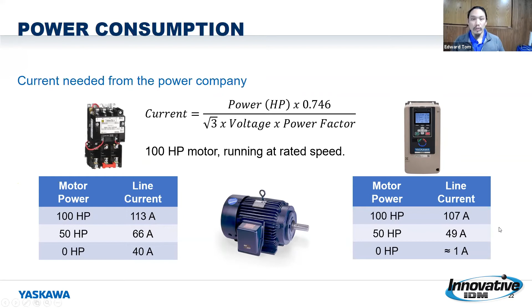On the VFD side, the reason why we're going to see lower line current is because that magnetizing current is still there on the motor side, but the drive will shield that a little bit, because now it's just circulating inside the drive. We don't need anything on the input side, so it just keeps recirculating in the drive. So now we only draw power when we need to. And that's the beauty of the drive, is that it only draws power when it truly needs to power that motor.